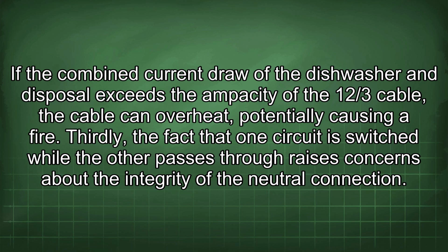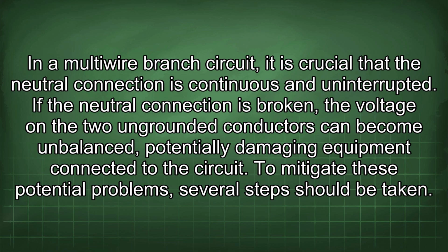Thirdly, the fact that one circuit is switched while the other passes through raises concerns about the integrity of the neutral connection. In a multi-wire branch circuit, it is crucial that the neutral connection is continuous and uninterrupted. If the neutral connection is broken, the voltage on the two ungrounded conductors can become unbalanced, potentially damaging equipment connected to the circuit. To mitigate these potential problems, several steps should be taken.